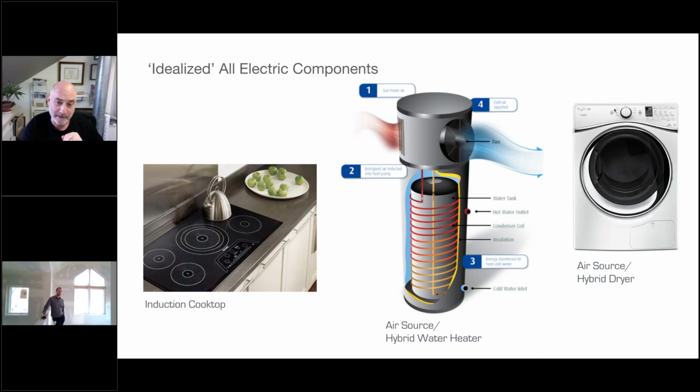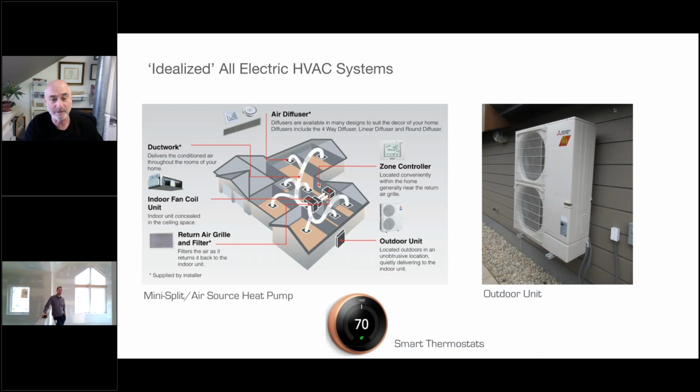And so the next part that is typical is the heating system. We like air source heat pumps. Ground source is another one that typically is all electric. This is a schematic showing an air source system, and you can see the outdoor unit. I would also point out on these outdoor units, do not mount them on the ground. They're not air conditioning condensers. These are for heating, so when there's a huge snow, that can be a problem. I know in Boston, they had a gigantic snowstorm about 6 years ago, right when people started putting in air source heat pumps, and they ended up having a bunch of them mounted on the ground, and they were buried under snow, and they didn't work. So we will raise them up to take that into account.